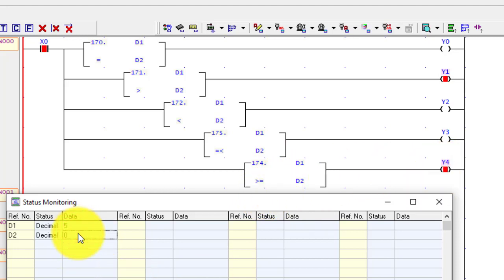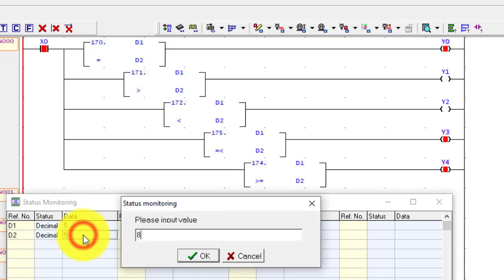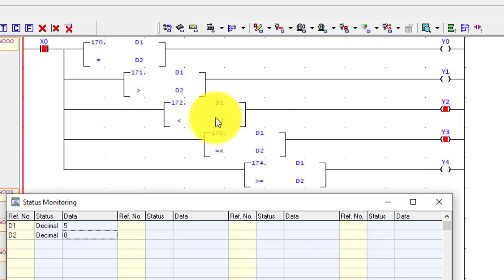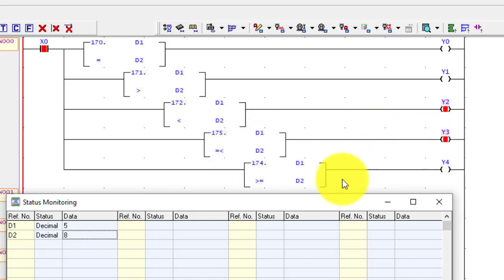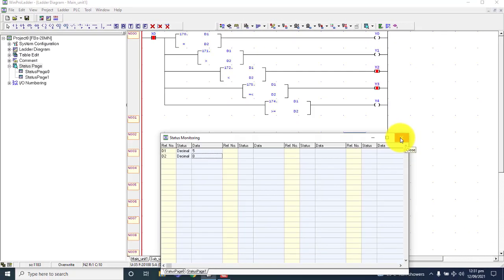I put D2 to 5 again — same condition as before: both values are equal, so Y0, Y3, and Y4 are on. When I increase D2 to 8, then Y2 and Y3 are on because D1 is less than D2, so Y2 is on. Y3 has the less-than-or-equal command, and since D1 is less than D2, Y3 is on. In this way you can use comparison commands according to your logic. If you have any questions, raise them in the comment box. Bye.